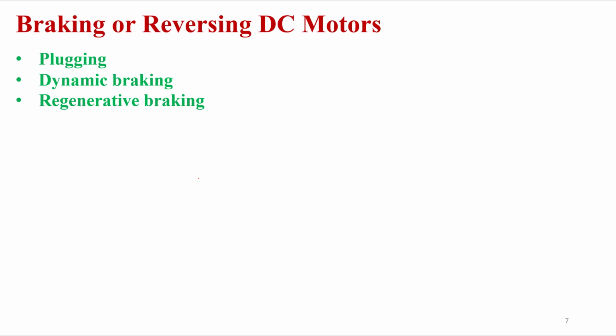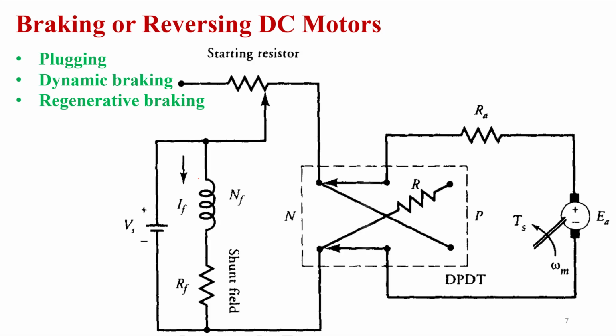Therefore, your back EMF will become greater than the supply voltage, and the motor will give power to the supply, feeding it to the supply system. By that means it is regenerating the power and feeding it to the supply. In that way also it helps to reduce its speed, right? So we'll see one by one.